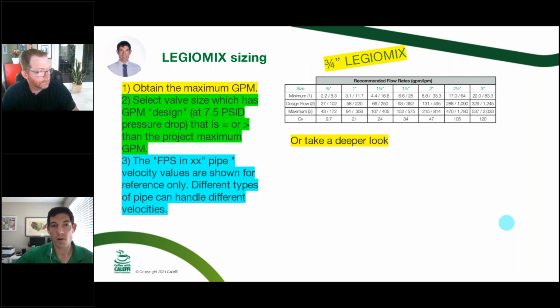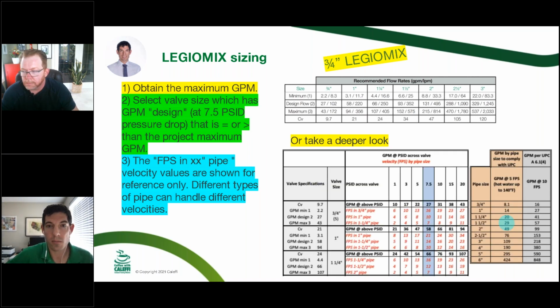So the easiest way to do it is to look at the recommended flow rates, and we'll say, okay, minimum is 2.2 GPM for that 3/4 inch valve on the top here. And then design flow of 27 is perfect. We were looking for 30 there. You could even go more wide open and hit 43 with the maximum there, because that CV is 9.7 for a 3/4 inch valve. That's pretty huge compared to the thermostatic that we looked at, even at a 1 inch size a minute ago, which was 3. So that's part of the reason that we can go down to a smaller size with the Legio mix.